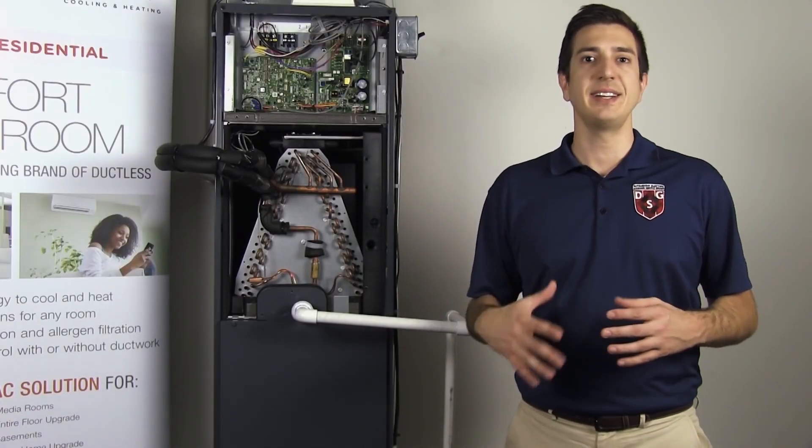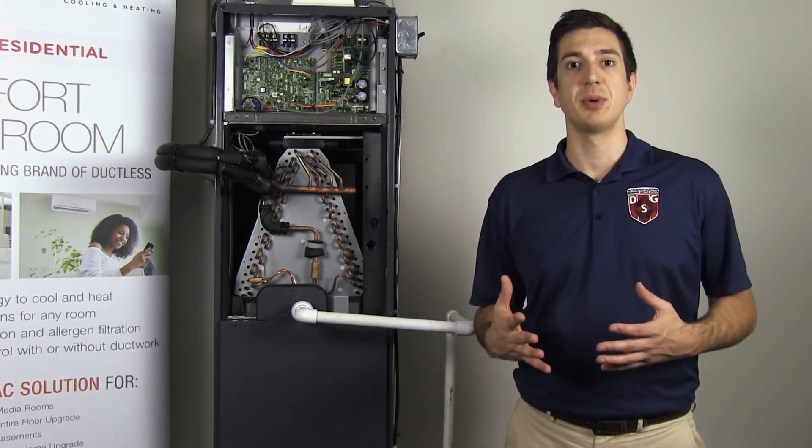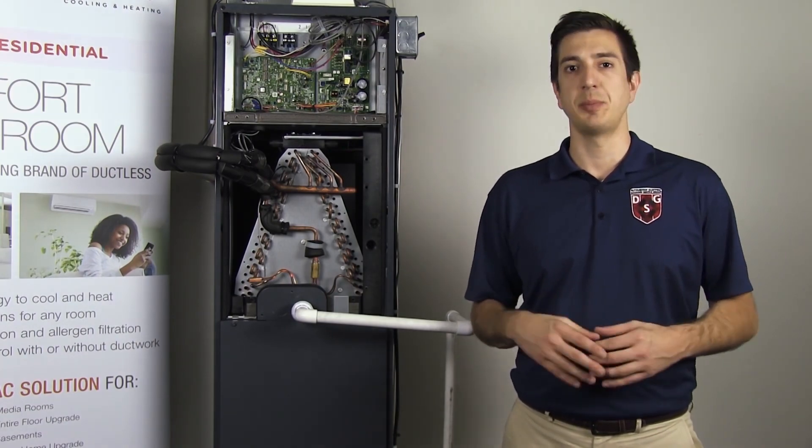In a nutshell, anything that would prevent the evaporator coil from changing temperatures in either the cooling or the heating mode could be the cause for the P8.